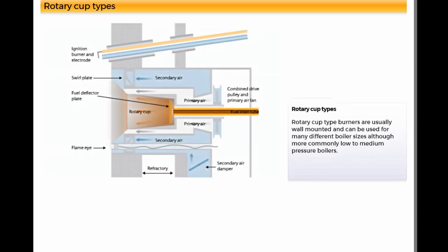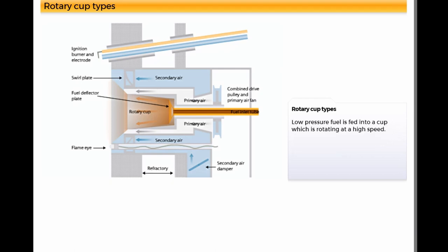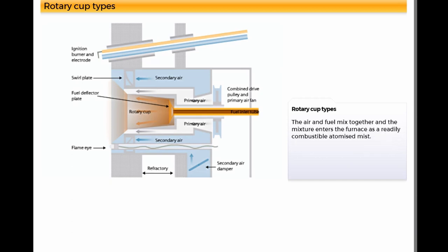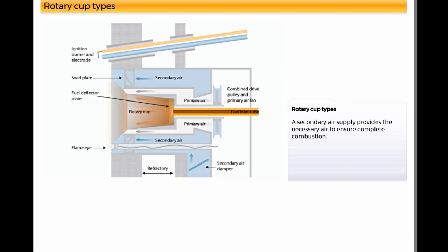Rotary cup type burners are usually wall mounted and can be used for many different boiler sizes, although more commonly low to medium pressure boilers. Low pressure fuel is fed into a cup which is rotating at a high speed. This causes the fuel to accelerate towards the periphery of the cup. As the high speed fuel atomizes as it leaves the cup, it is picked up by a primary air stream, which is directed parallel to the outside of the cup and towards the furnace. The air and fuel mix together and the mixture enters the furnace as a readily combustible atomized mist. The secondary air supply provides the necessary air to ensure complete combustion.